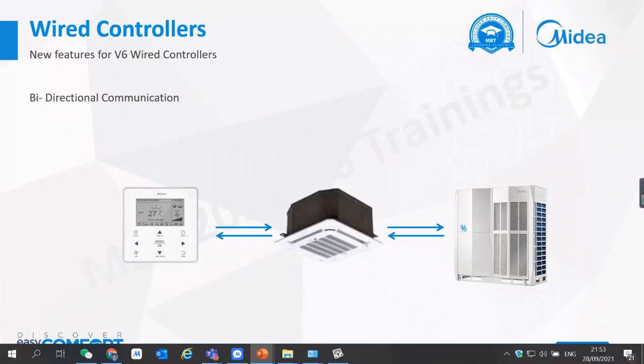What are the other information flowing from the indoor unit back to the controller? So we can get parameter values for the indoor unit at the controller level. What kind of parameters? Sensor values. What are the sensor values of the indoor unit? So for the indoor unit, maybe you know that we have three sensors like T2, T2B and T2A sensor. What are the values of these sensors? EXV opening degree, right? Cold draft prevention, these kind of settings you can check directly from the wired controller now.